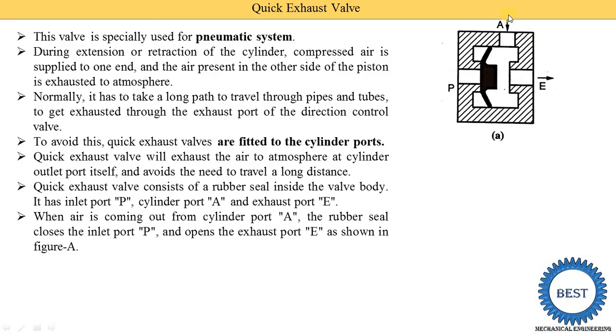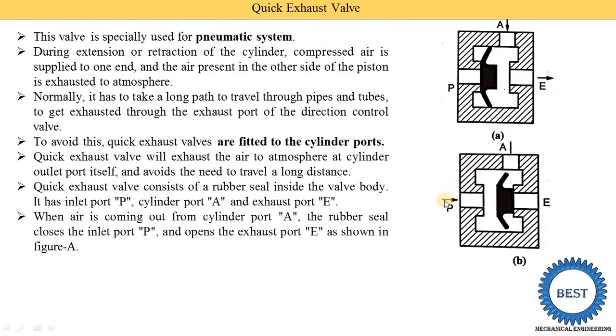As shown in figure A, the arrow near the A port indicates exhaust air coming from the actuator or cylinder entering the A port. When air comes from this side, the rubber seal moves to the left, closing the P port. The air coming from the A port is then supplied to the exhaust port E and from there released to the atmosphere. When compressed air is supplied from the compressor to the P port, the pressurized air moves the rubber seal toward the exhaust port, closing it.